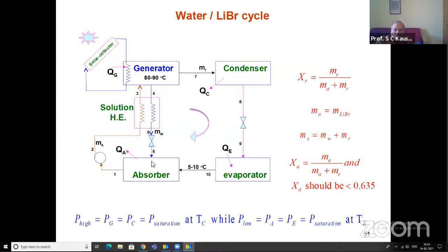So at state point 6, there is a problem of crystallization for water lithium bromide because the pressure is reduced and the temperature is low, so lithium bromide crystallizes. And the limit is that when the absorbent concentration reaches 0.635, there is a problem of crystallization. So we have to maintain the operating conditions in such a way that the concentration of the solution is never more than 0.63. If it is more, then there is a problem of crystallization here.